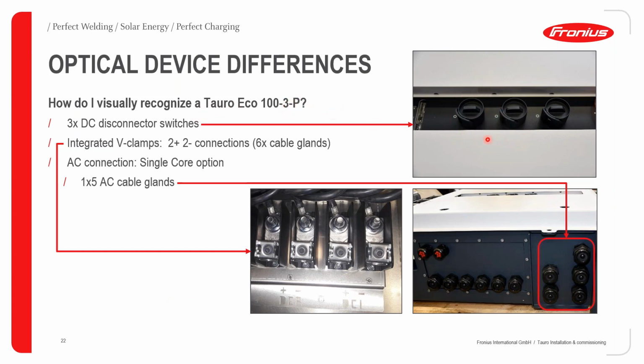On the front panel, you can see 3 DC disconnector switches, and we also have the pre-combined DC connection area that is clearly labeled with engravings for plus and minus. So it should not be that you make any connections with reverse polarity here. It's clearly labeled for DC1 and DC2. You can see where you are going to connect your appropriate DC cables.